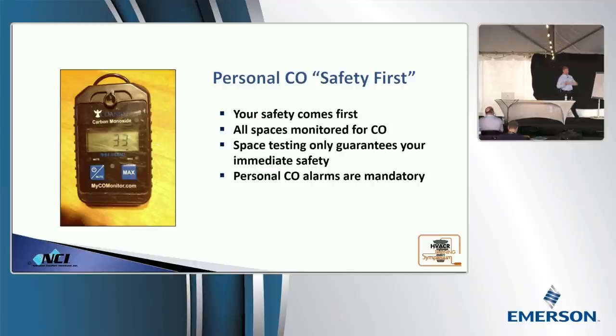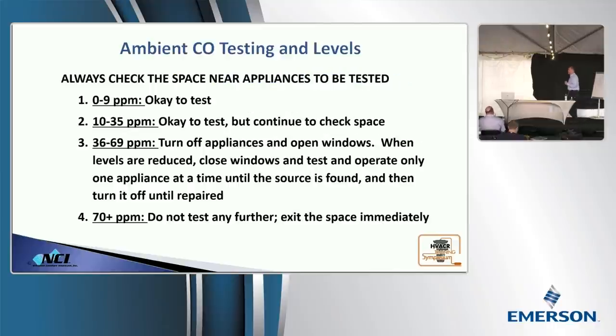A lot of guys will go in, they'll say, oh, you've got X amount of CO, this is your problem. You cannot pinpoint a CO problem with ambient CO testing alone. Ambient CO testing tells you that there's a problem. It doesn't tell you where. If you measure CO in a return duct or in a supply duct, it tells you that the blower and the equipment is circulating airflow. It doesn't indicate the source. So ambient CO is for your personal protection. Now, John Ellis went over this yesterday in his session. Some of the levels that you guys need to be aware of.